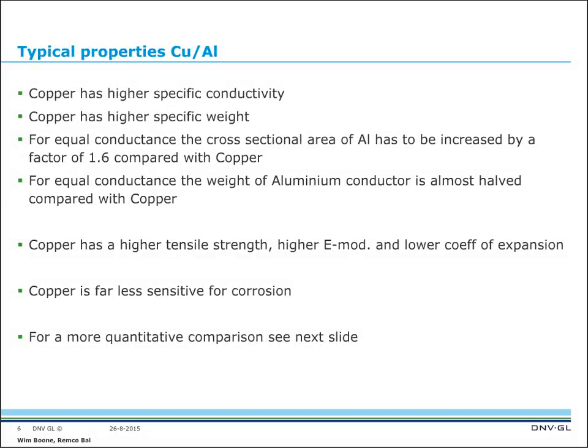Copper has a higher specific conductivity and a higher specific weight. For equal conductance, the cross-sectional area of aluminum has to be increased by a factor of 1.6 compared with copper, but the weight of an aluminium conductor is almost half compared with copper. Copper has a higher tensile strength, higher E modulus, and a lower coefficient of expansion, and copper is far less sensitive to corrosion.